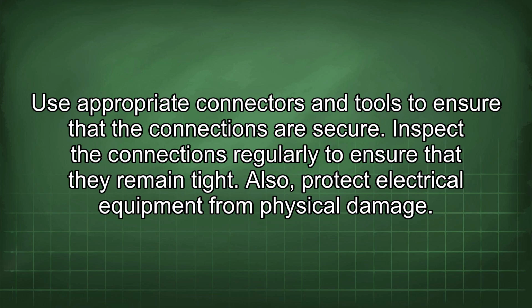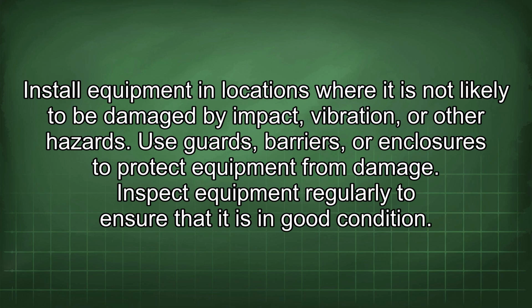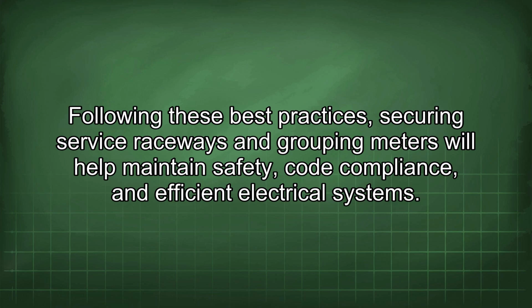Also, protect electrical equipment from physical damage. Install equipment in locations where it is not likely to be damaged by impact, vibration, or other hazards. Use guards, barriers, or enclosures to protect equipment from damage. Inspect equipment regularly to ensure that it is in good condition. Following these best practices, securing service raceways and grouping meters will help maintain safety, code compliance, and efficient electrical systems.